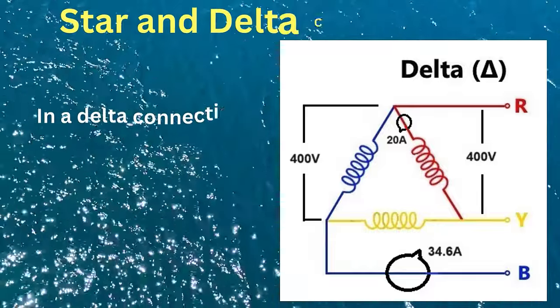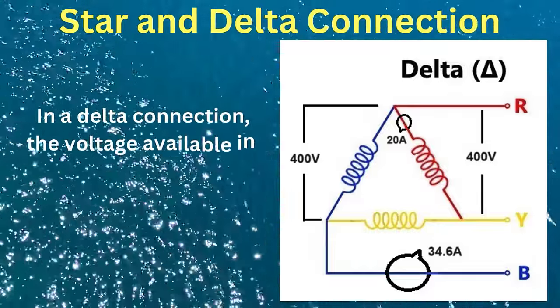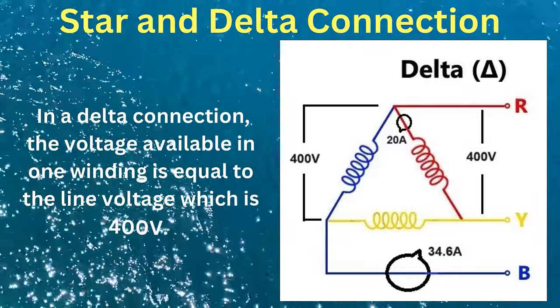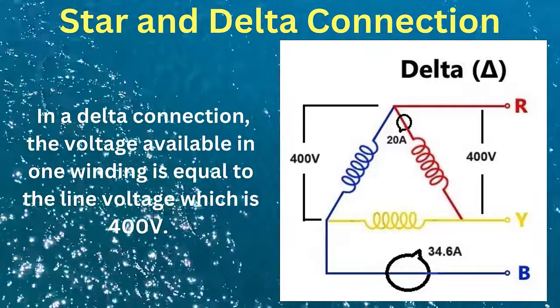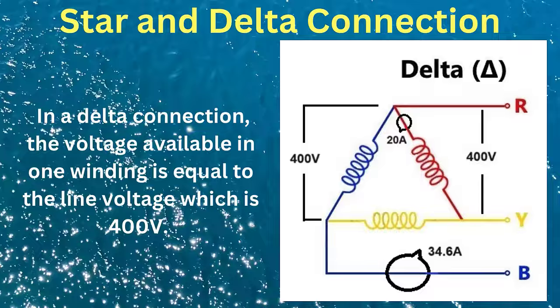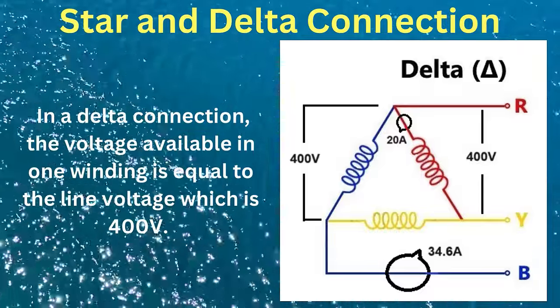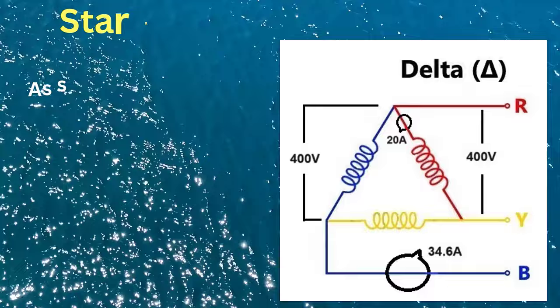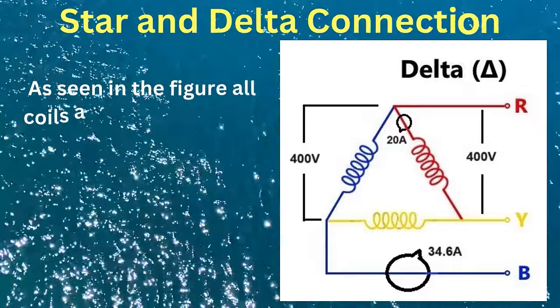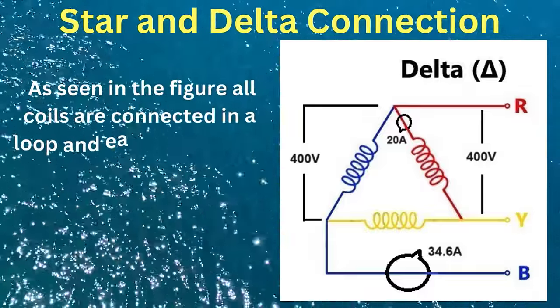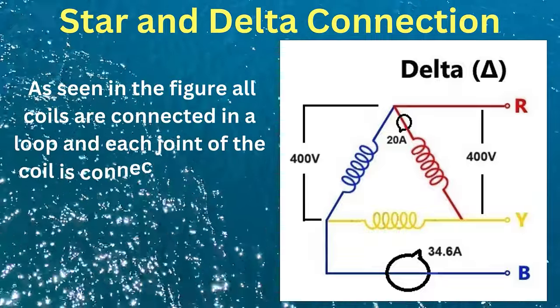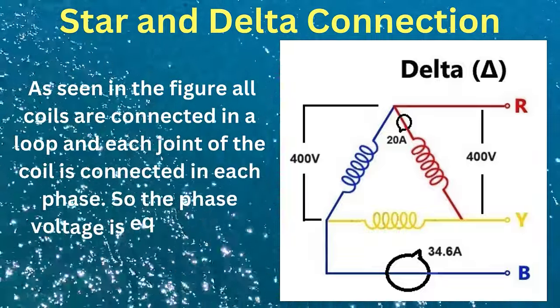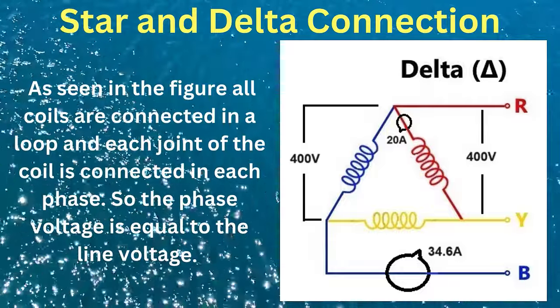In a delta connection, the voltage available in one winding is equal to the line voltage, which is 400 volts. As seen in the figure, all coils are connected in a loop and each joint of the coil is connected to each phase. So in delta, the phase voltage is equal to the line voltage.